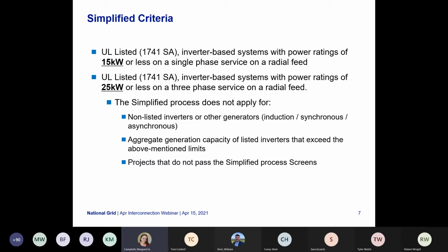So simplified applications have a total system size of 15 kW or less for single phase and 25 kW or less for 3-phase. These system sizes are the total system size, including solar plus AC storage. In addition to qualify for the simplified process, the application must be UL 1741 SA listed, and the project must pass the simplified screening process.